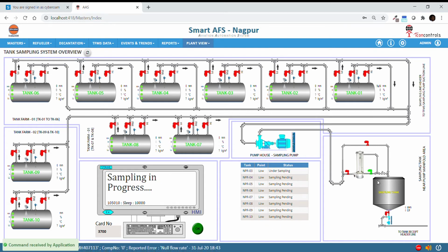and post that we see that this particular SOV is open. That means all the contents of the glass jar will get drained. Then we see that the pump has started and the tank 3's low point is open and the bypass line is active. So that means all the line product gets flushed, so that we have new product in the line from the tank 3's low point.